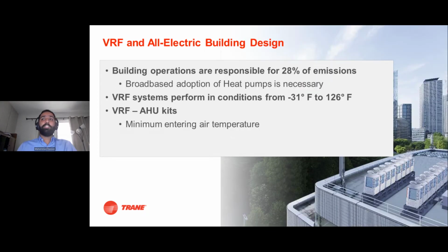So as Ryan previously mentioned, there is a larger electrification push within the construction industry, which is pushing us for broad-based adoption of heat pumps in order to enable grid-scale decarbonization. VRF systems are ideal for this, primarily because they're electrically driven, but they also operate in a wide range of ambient conditions. So we now have condensing units that can run from -31 Fahrenheit in the heating season all the way to 126 Fahrenheit in the cooling season. And so this makes VRF systems very applicable for a wide range of geographical conditions within the country.